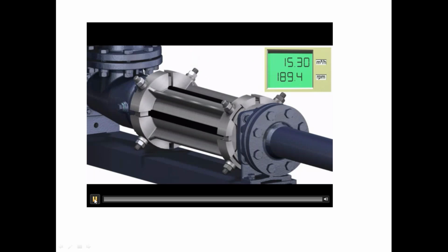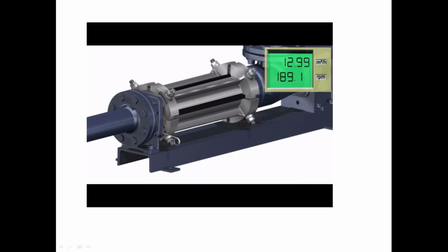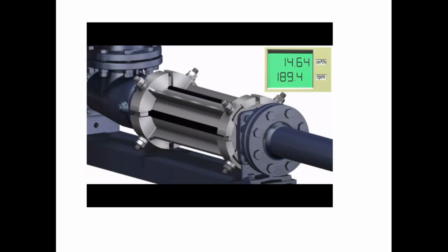There's only two tools that are needed to work on this pump. One is a wrench, and two is a pair of circlip pliers. Again, we're showing that it's basically like a tire. The end user would tighten all of these bolts equally around the pump. The pump is running, and you can see the flow increase in the line. Without compression, this pump technology does not work properly.